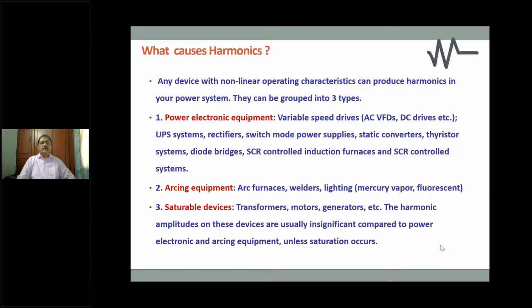You see, any device that produces a non-linear operating characteristic will produce a distorted waveform, which is what is called as harmonics. So typically, you know what is a sinusoidal shape of a waveform, AC current, alternating current. Whenever that shape is disturbed or distorted, we will call it as the effect of harmonics. So this harmonic can be grouped into basically three types of being generated by three types of equipments. So power electronic equipments like variable speed drives.